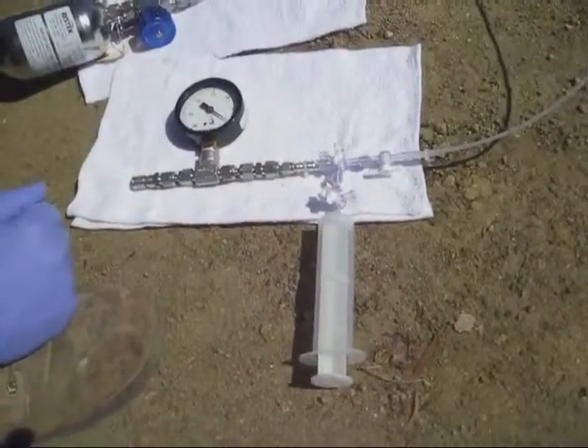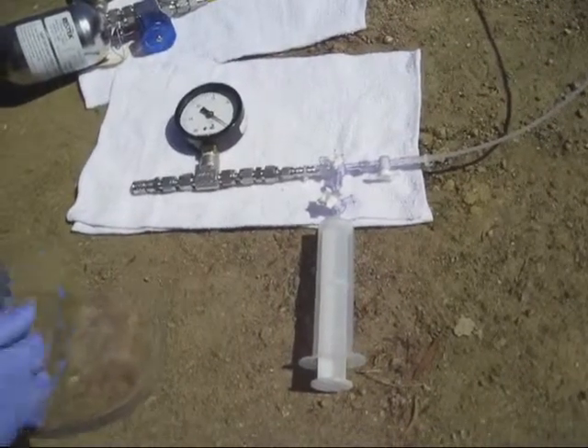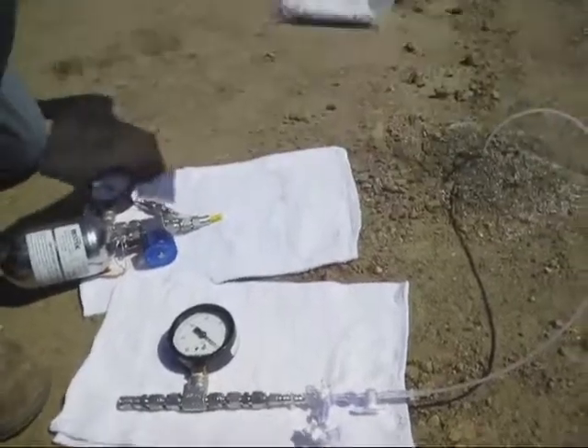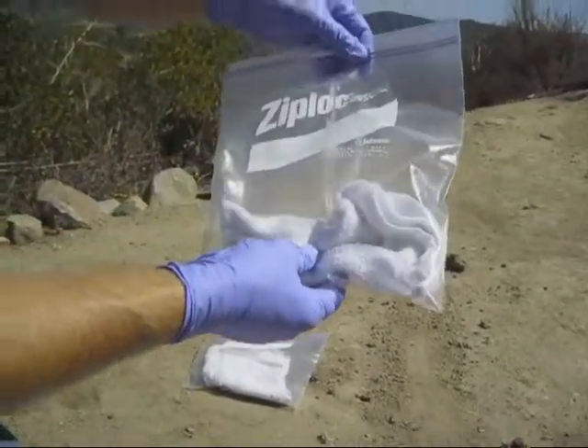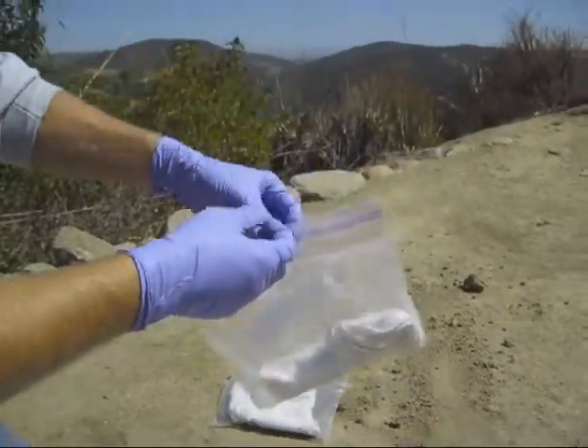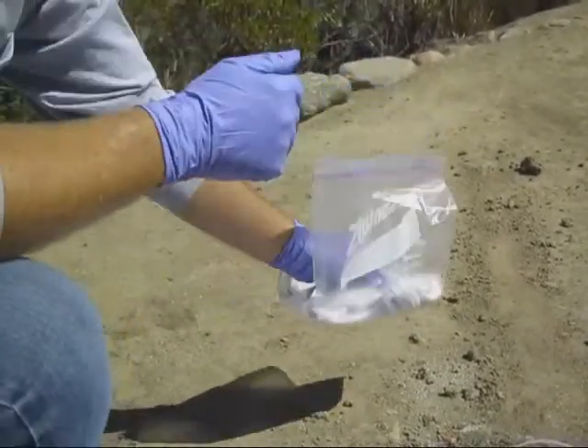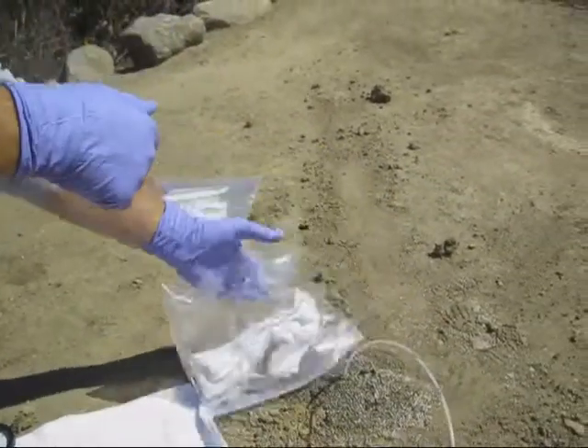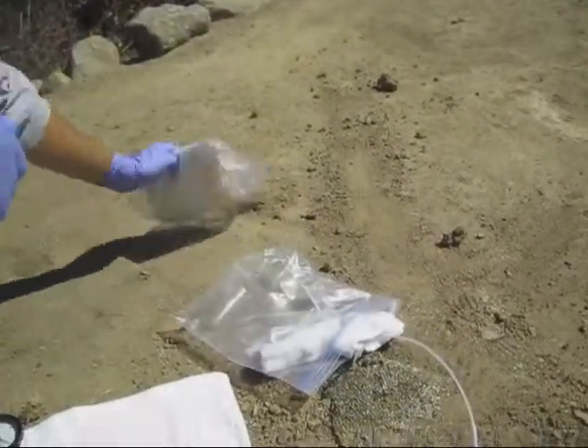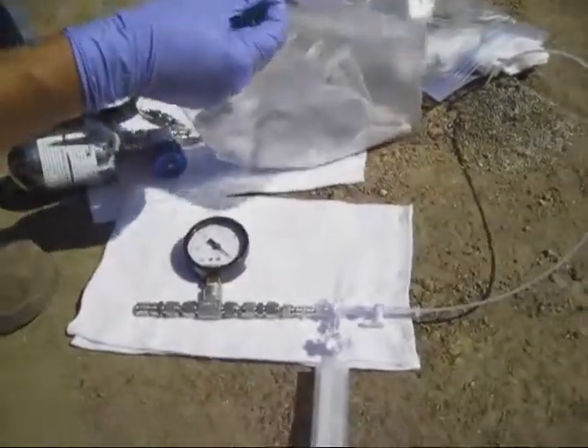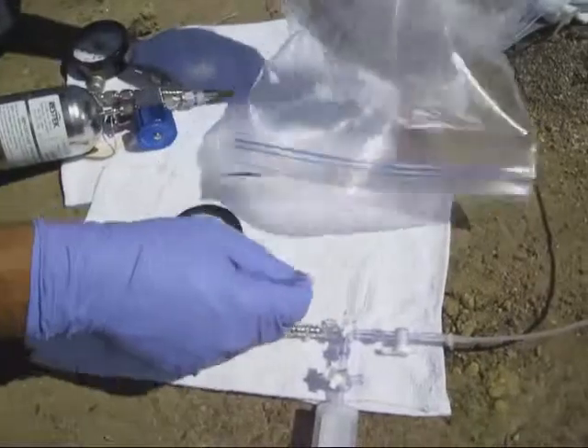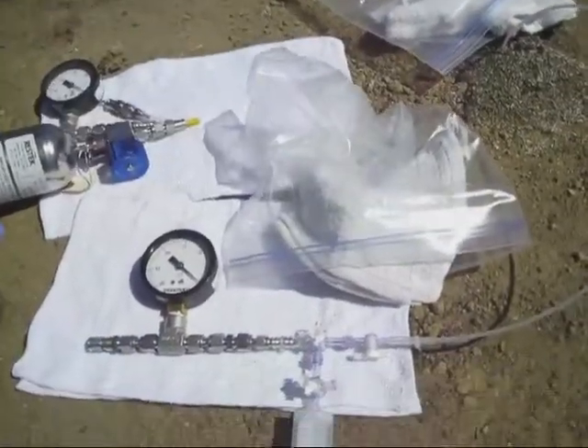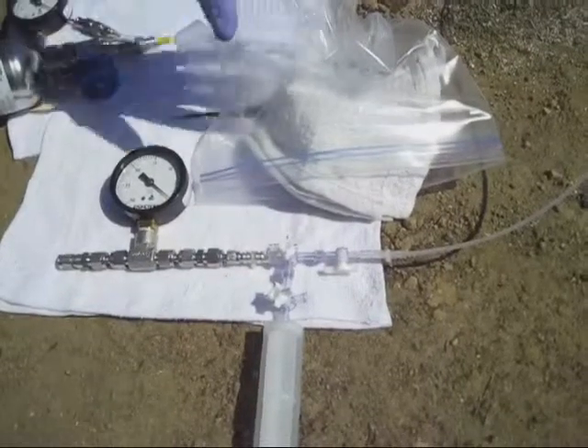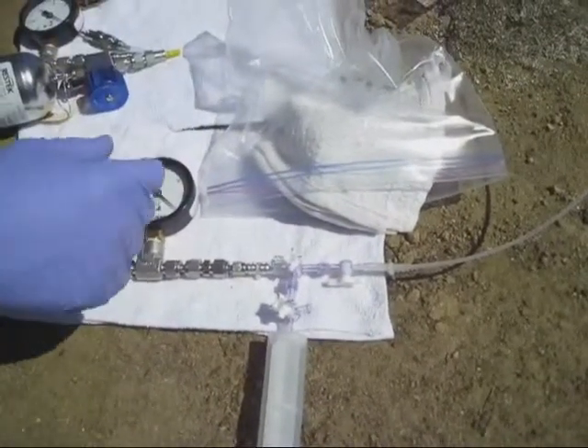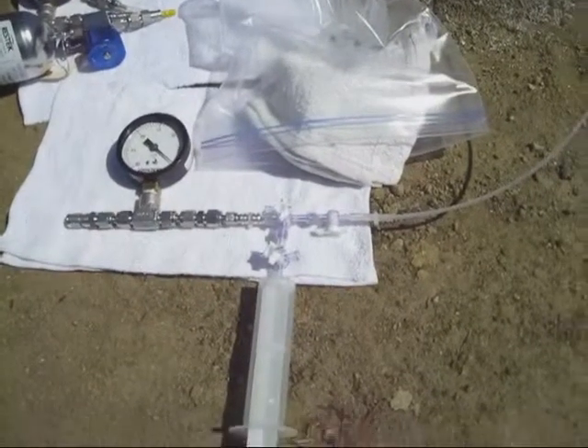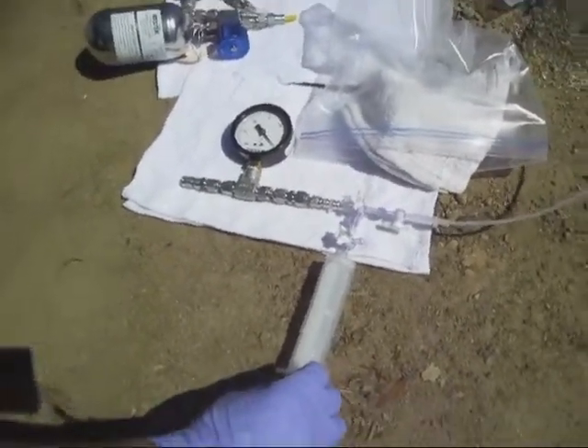Before I do that, I'm going to lay down a leak check compound. We sprayed these bags with a liquid leak compound, and we're going to place one of these at the base of our probe. This is going to detect for any leaks that we have on our probe, the integrity of our probe. And if you so choose, you can place a second bag, open it up, and place it around your fittings as a double check to make sure all your fittings are tight. The idea is if any of the known compound that we sprayed on the rags shows up in our sample, we know that we've drawn it in through leaks in our fittings. So we've got our leak check down. Now we're ready to purge the well.